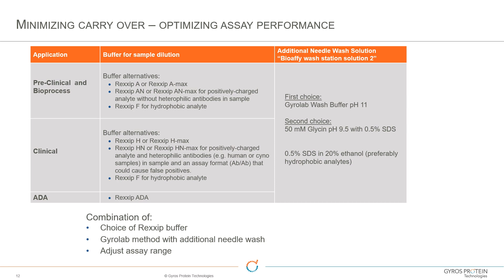A 1.5 M sodium chloride in 20% ethanol solution has also been used, but it can clog up the needles and wash station if you're not careful. Maintenance is very important, especially when dealing with sticky analytes. You want to ensure needles are getting cleaned for the robustness of running many assays on the system, and also that you're not having any contamination of the wash station or problems with the wash station function.